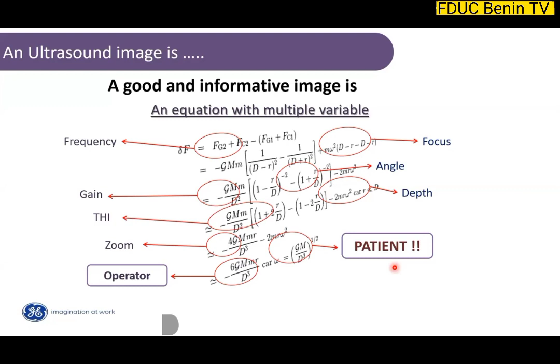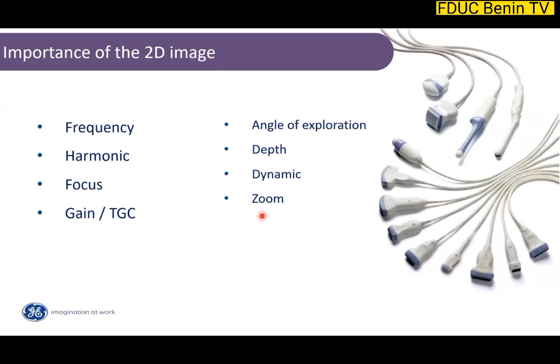So these are the elements that we can play with in order to improve our 2D image quality. The frequency, of course, the harmonics, the focus, very important, the gain and the TGC, the angle of exploration, the depth, the dynamic, and the zoom. All these elements can impact your 2D image. Let's start with the focus.